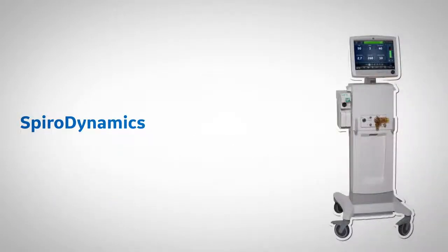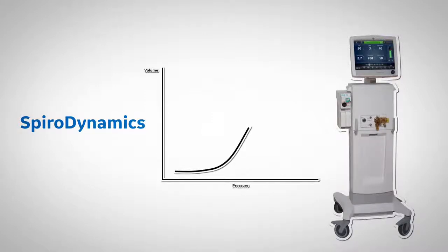SpiroDynamics is a CareScape R860 clinical decision support tool which draws a dynamic pressure-volume curve breath-by-breath regardless of the volume or pressure control modes of ventilation.